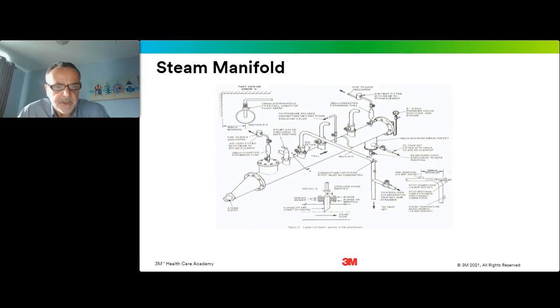So this is a steam manifold. You find a picture of this in the UK guidance, the Health Technical Memorandum number 10. Basically, this is a long piece of pipe. At one end, the steam from the hospital supply or the boiler passes into this pipe. It will have a couple of points in it which allow venting of any non-condensable gases, and these are mounted on the top of the pipe. You can see them here. And then at the bottom of the pipe, you will have a sump which will collect any condensate that has occurred during the steam transportation, and that will then allow the condensate to flow away.